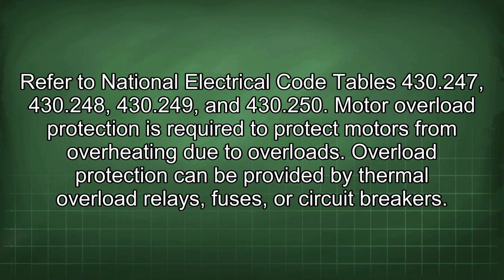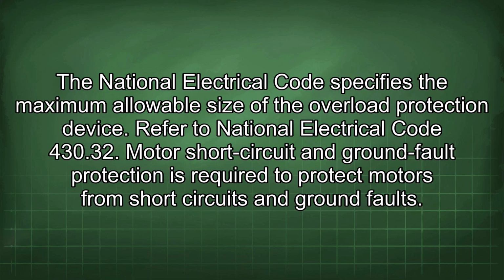Overload protection can be provided by thermal overload relays, fuses, or circuit breakers. The National Electrical Code specifies the maximum allowable size of the overload protection device. Refer to National Electrical Code 430.32. Motor short circuit and ground fault protection is required to protect motors from short circuits and ground faults.